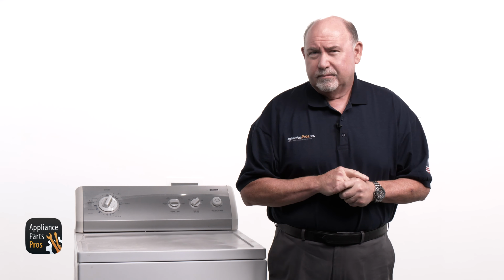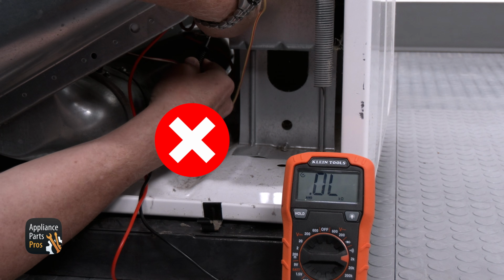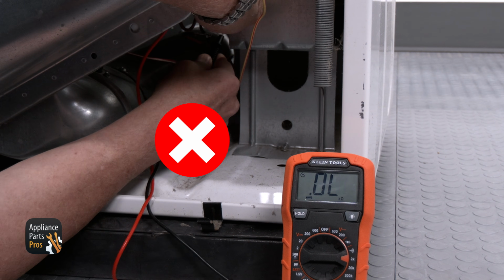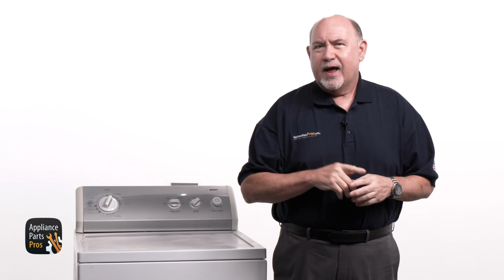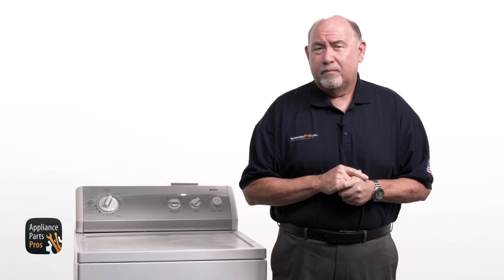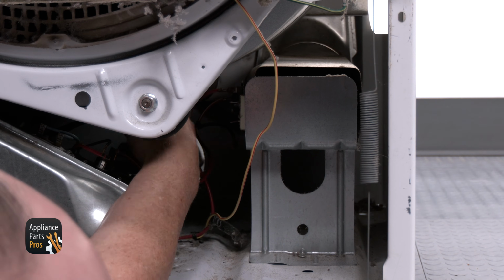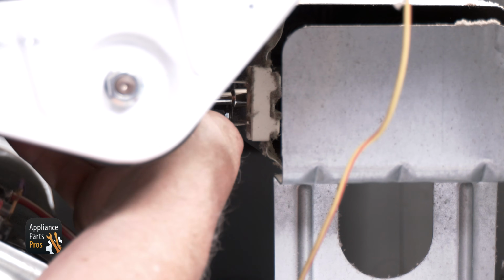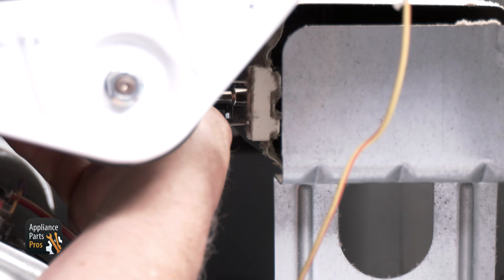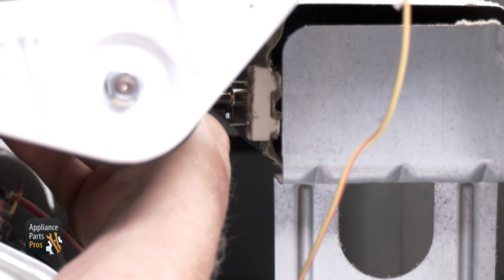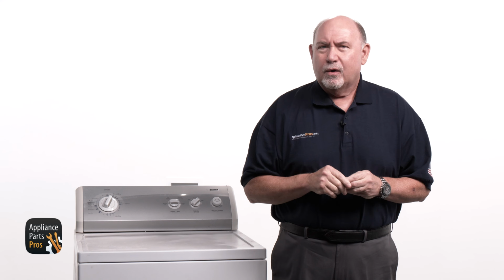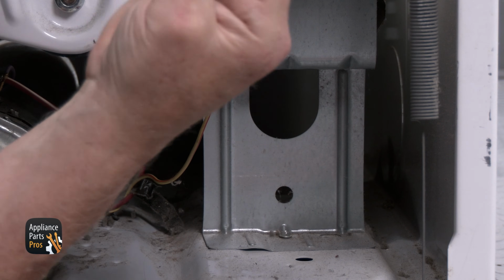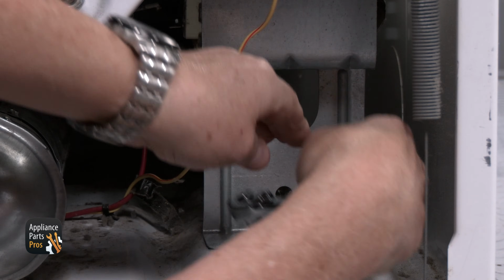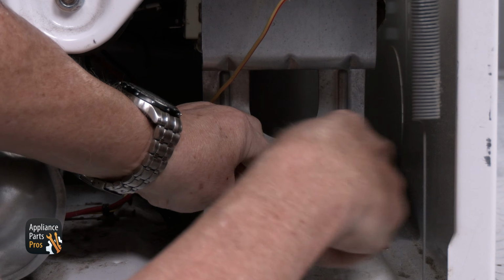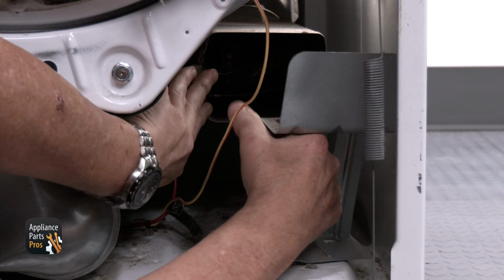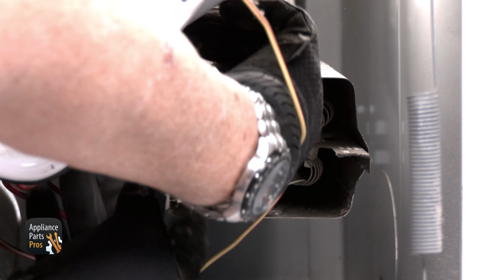After making our 3 checks, we found out the heating element on this unit was defective. Let me show you how to replace it in case you have the same problem. First, we need to remove both wires from the element. Next, find the single 1/4" screw on the side of the element box just in front of the terminals. You'll need to use the 1/4" socket or nut driver to remove it. There's another 1/4" screw in the front of the heater box which holds the shield in place, and you'll need to remove this one too. Now pull the heater all the way out.